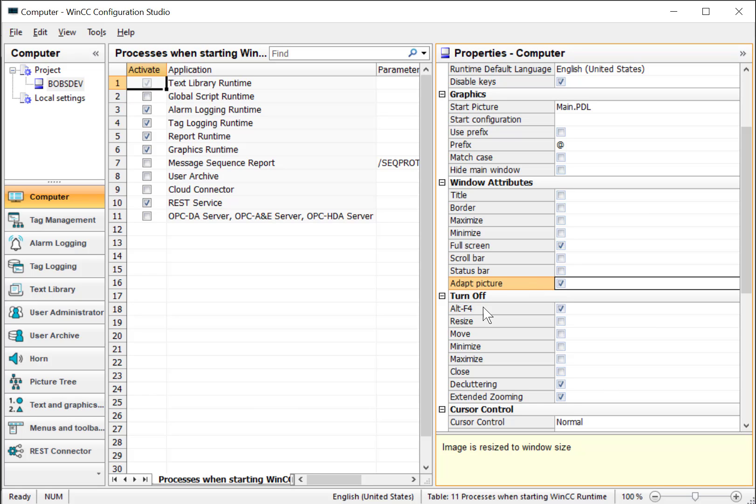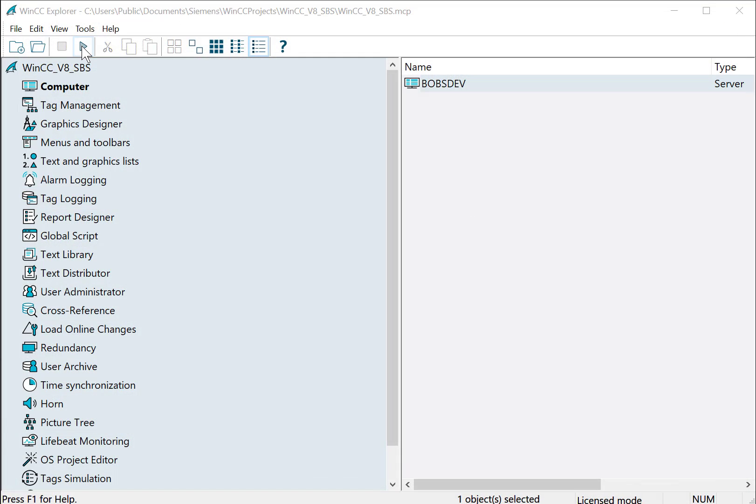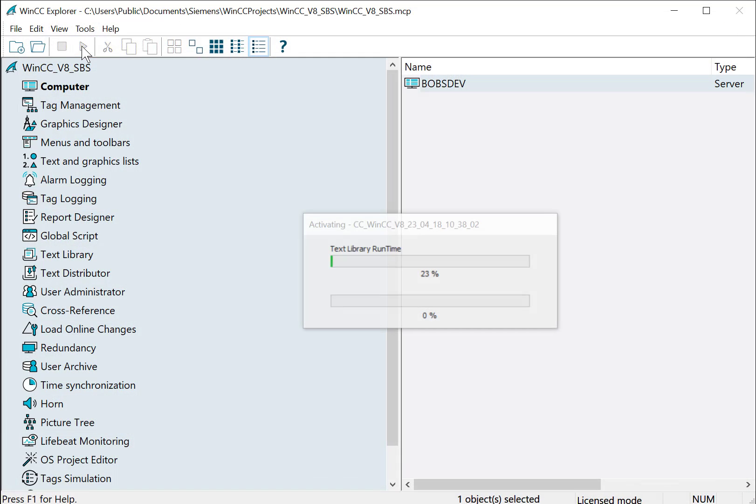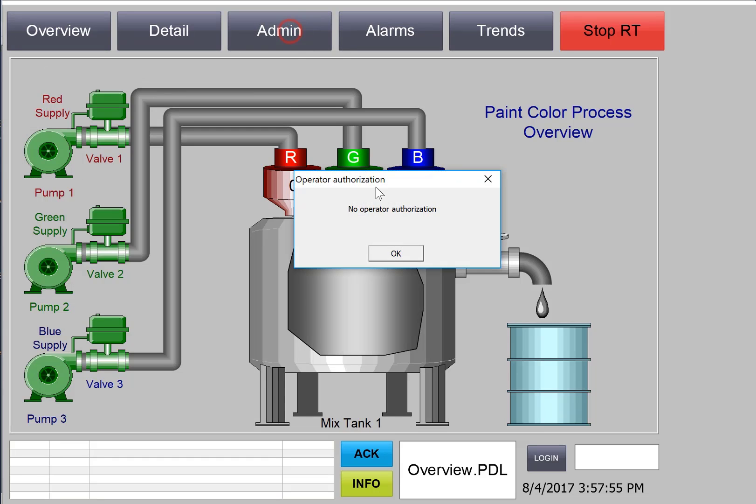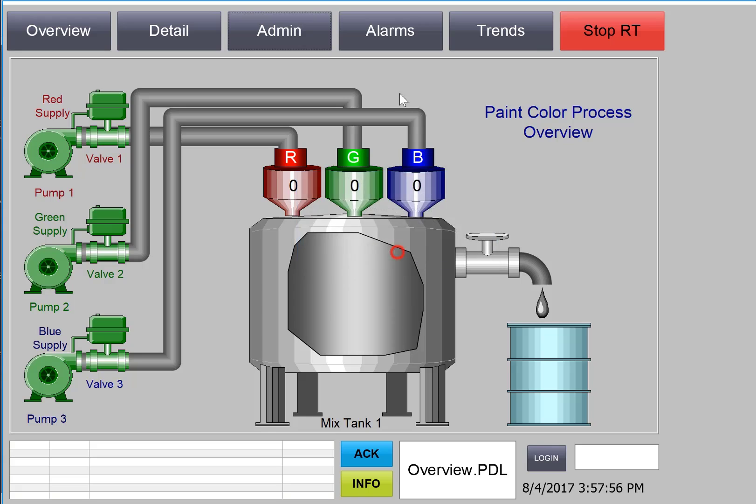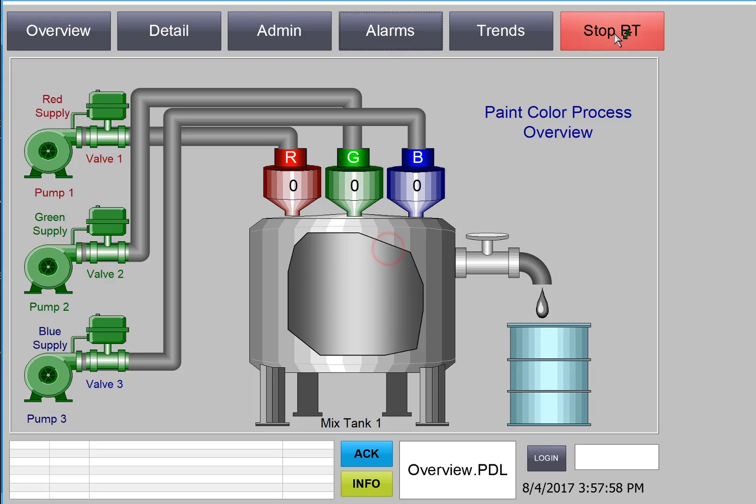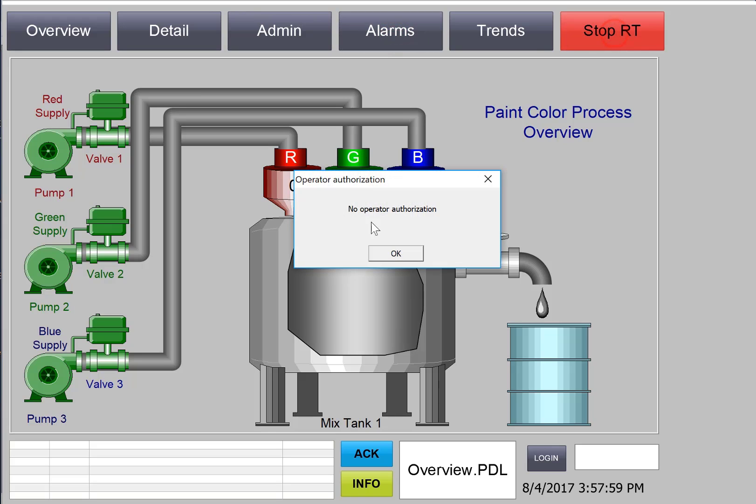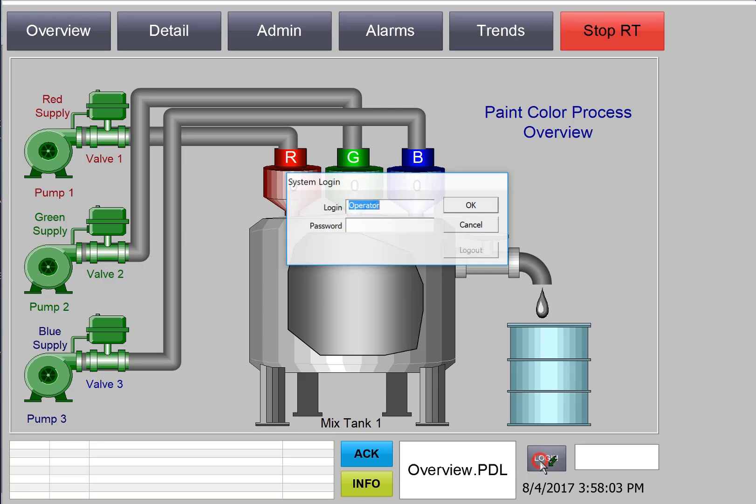We're going to turn off Alt-F4. Alt-F4 basically is like clicking the red X on an active window and it closes that window. So we want to make sure they can't hit that keystroke. Now we can close this and from WinCC Explorer we can start runtime. So you can see the runtime window is full screen and I am locked out of doing things, especially like stopping RT.